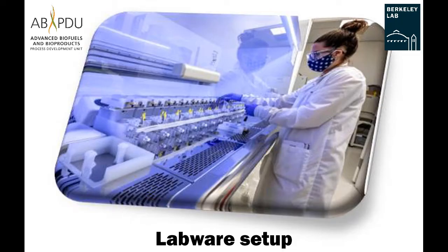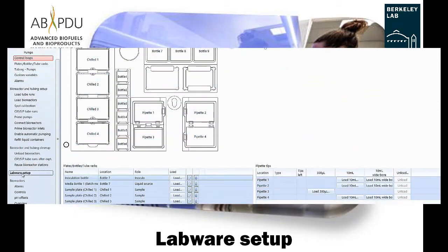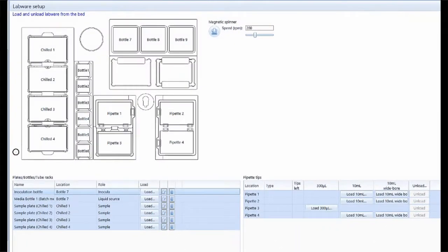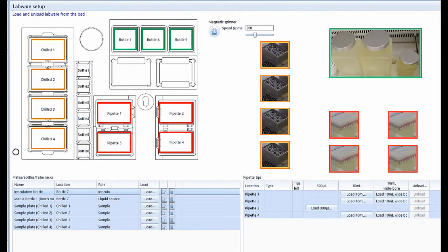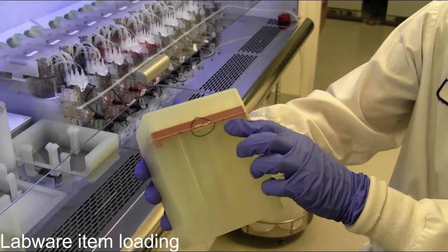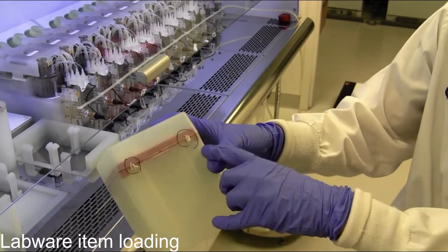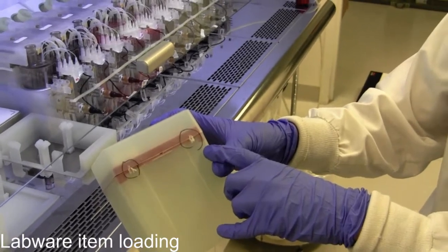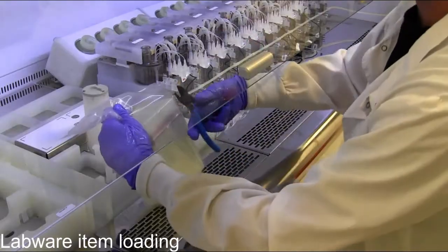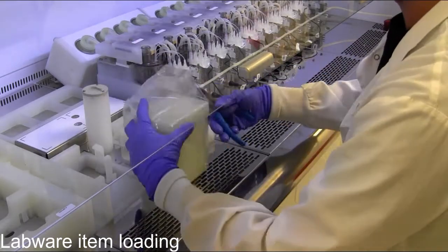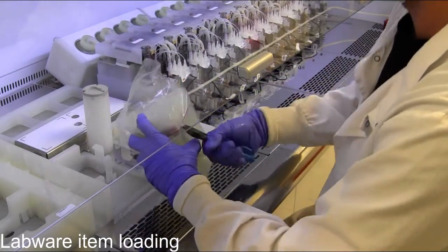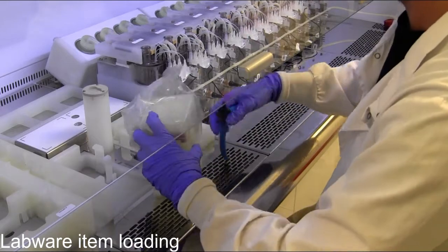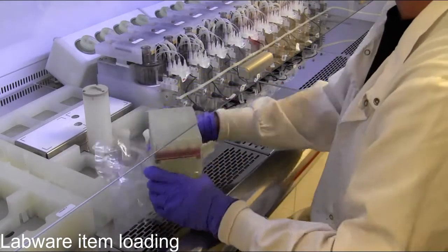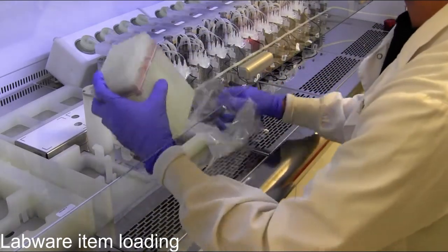Labware setup. Labware items like tips, reagent bottles, and sample tubes need to be loaded to the workstation. Off-brand tips require a few minor modifications to the box lid to make them compatible with the liquid handler. Cut off the front clip and 2 hinges in the back, and load the box in one of the tip box positions.